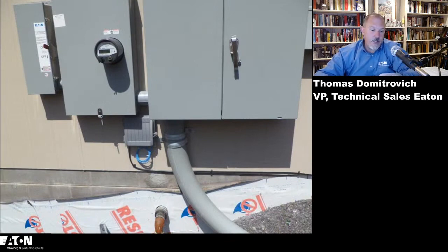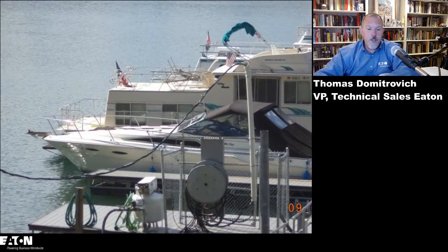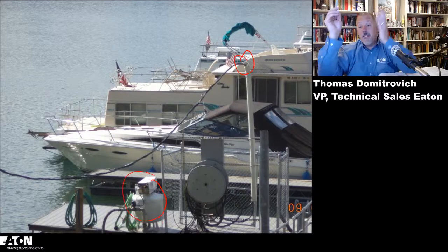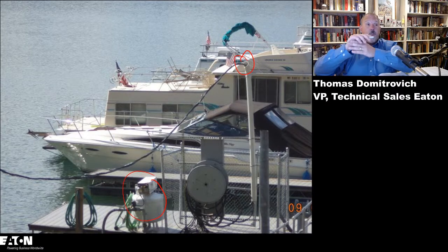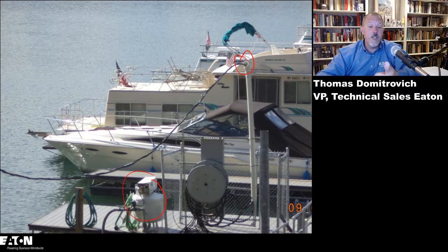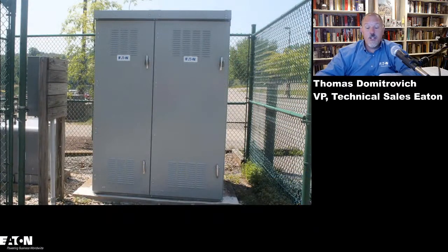So this is, you know, again, an example. This is onshore. And there are requirements now in 555 that deal with overhead conductors that go down to the marina. So this is an example of overhead conductors that serve a pier. And there's another shot of that where they come up and out. And, you know, this is actually a station where they have propane. This brings in another issue. You know, the fact that chapters 1 through 4 apply generally, and chapters 5 through 7 can amend chapters 1 through 4. There are HAZLOC locations on top of these because we've got fueling stations, you've got propane stations, things of that nature. So you have hazardous locations in addition to your standard requirements.